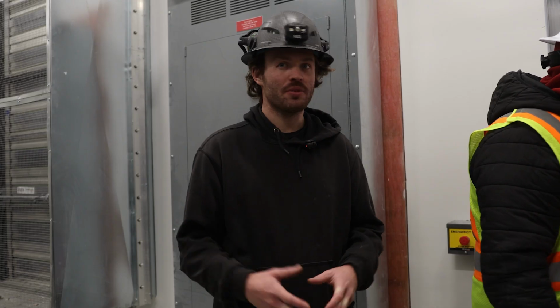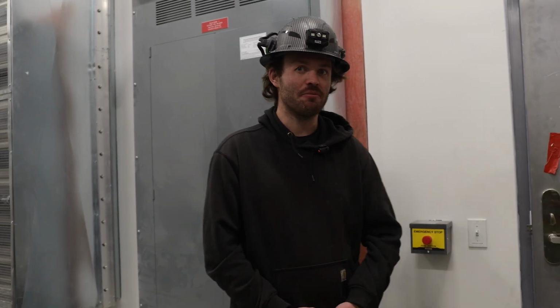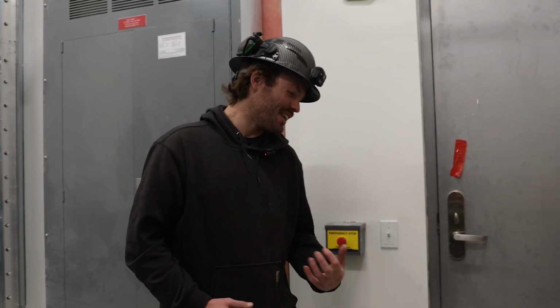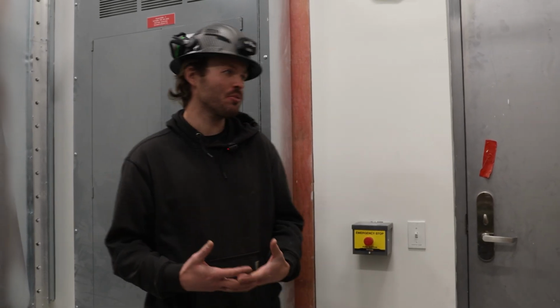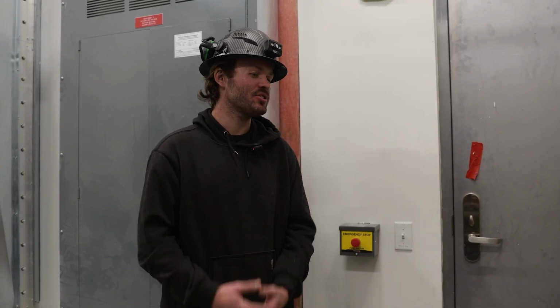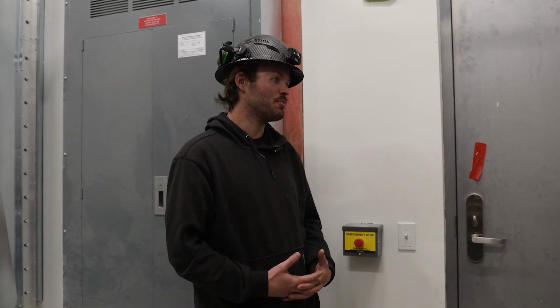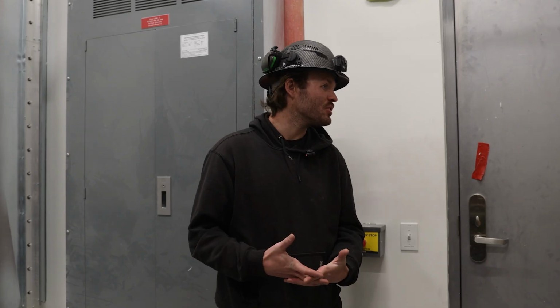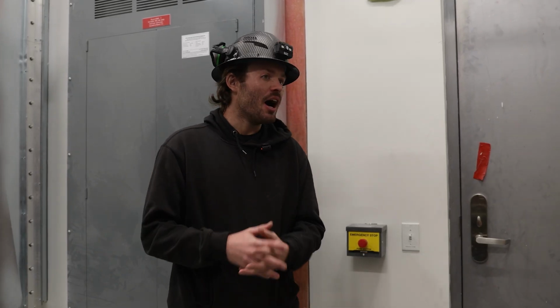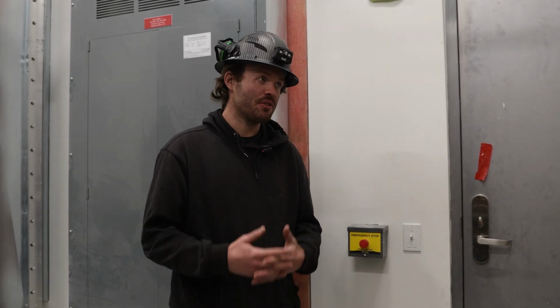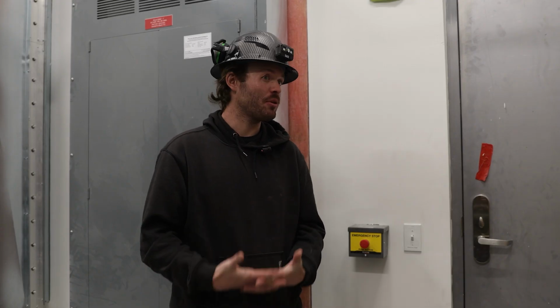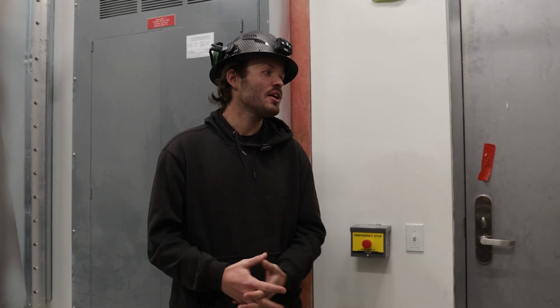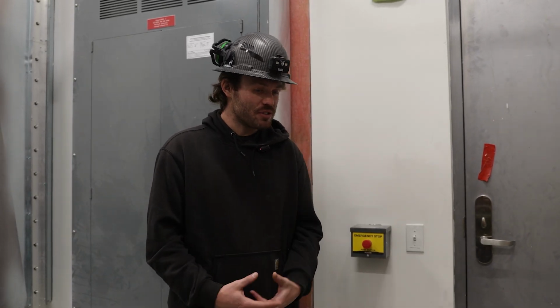Realistically, he was asking about the fire alarm panel and the procedure leading up to a monthly inspection, on contacting the alarm company. So what you want to do is call the alarm company and let them know, hey, I'm doing generator testing today. Can I get troubles and supervisories offline for 3 hours? Gives you tons of time. Fire protection doesn't need to come off. Realistically, you probably want fire protection on in case something happens. So just troubles and supervisories.